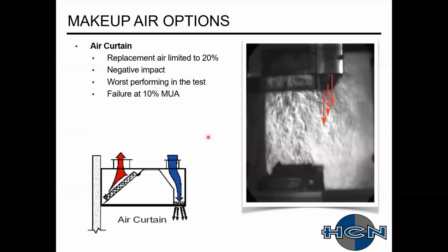Air curtain was actually one of the poorer performers. If you have one of these types of hoods, you have to account for that velocity coming down, because what happens is it's going too fast. It's basically doing the same thing that we talked about before, that effluent kind of circles around. This is nice, cooler air. This is going to pull it out and then drop it right into the space.